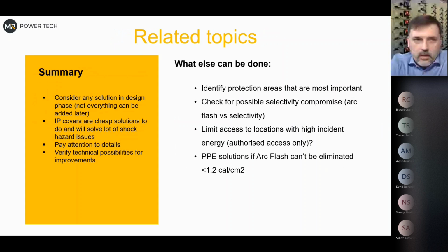So that's all for today. As a short summary, I would say: consider any solutions in the design phase, because sometimes you will not be able to add things later. You might have a new switchgear that will not be able to expand. Consider an IP cover, it is a very cheap solution, and it's not only protecting against arc flash, but also, which is more important, against the shock hazard, the electrocution situation. So consider this, and pay attention to details, especially on the study level, but also on how you execute things.